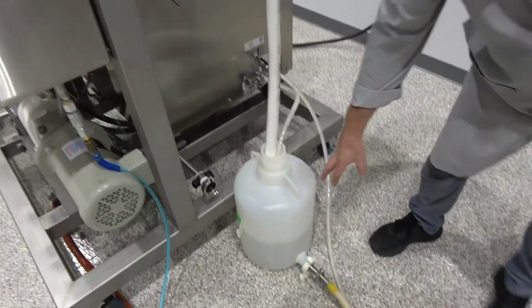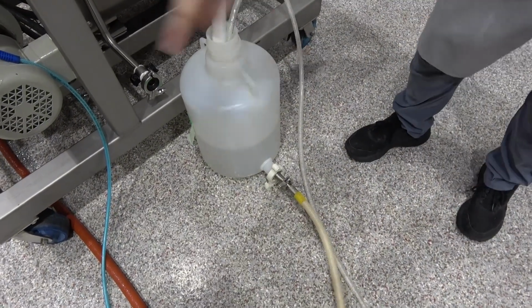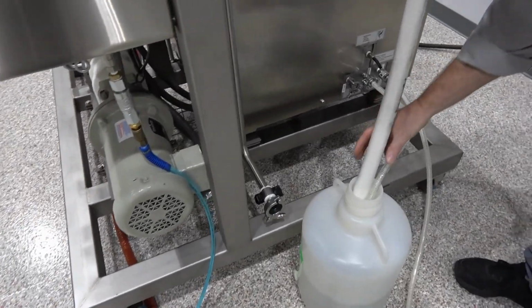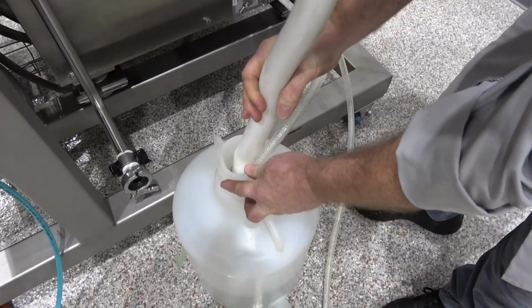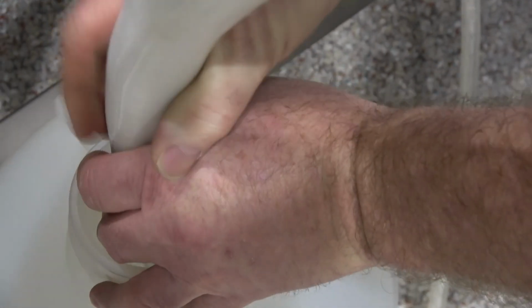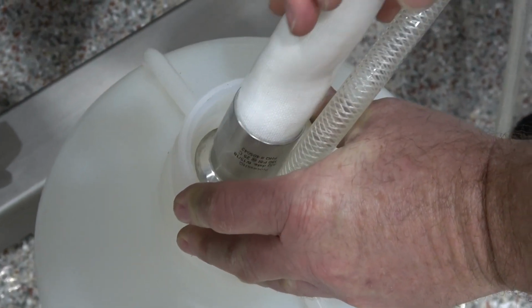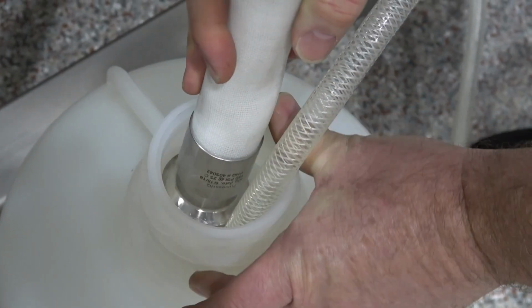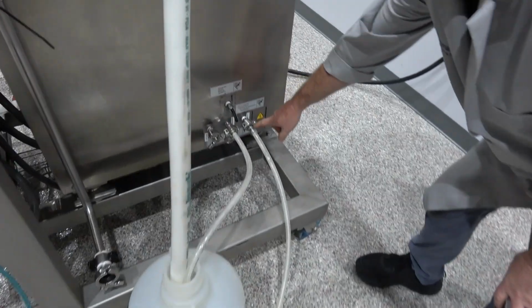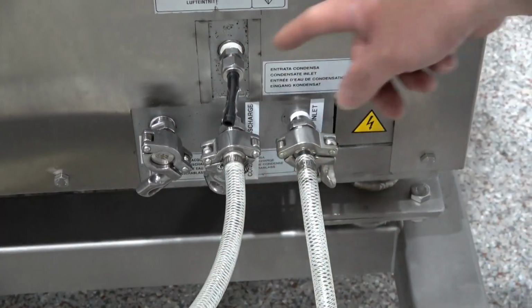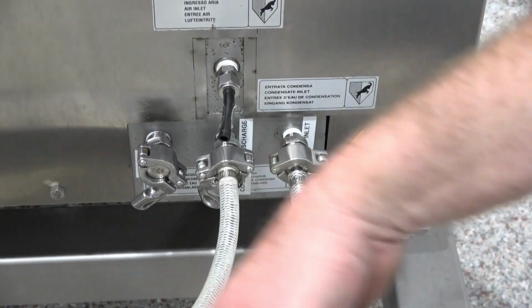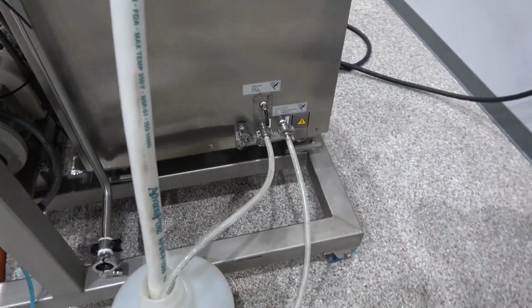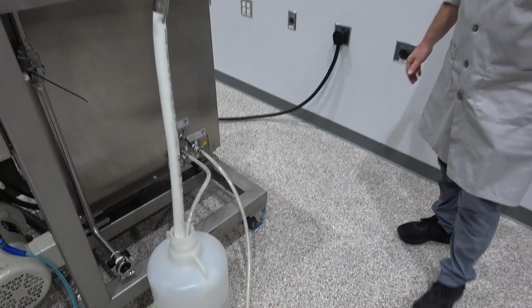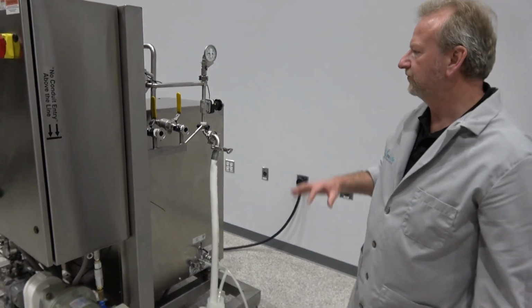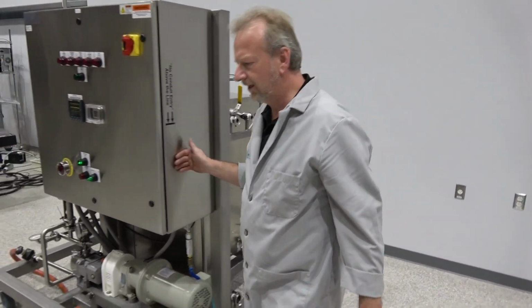We're pulling from our jug here, and it's pulling into the diaphragm pump and then taking it back over, and then we're moving fluid here. I'll just pull this out here so you can see. I know I got this kind of tucked down in there, but you can see the flow coming out there. It's nice and warm. I don't want to pull it out and make a mess. And then I'm also using my flushing fluid, or what I call condensate fluid. It's just flowing in and back out too. And that does have to be running, or you'll throw an alarm on that. But anyways, just a really nice running machine, really super clean, ready for some production.